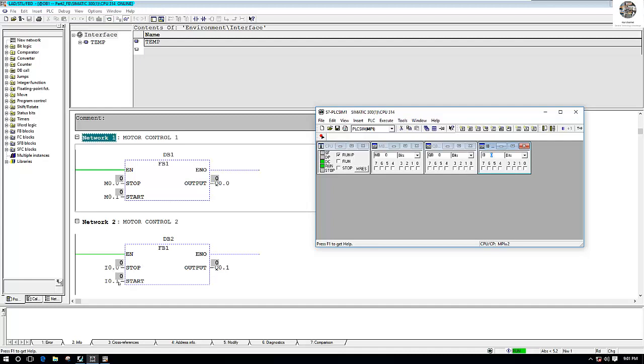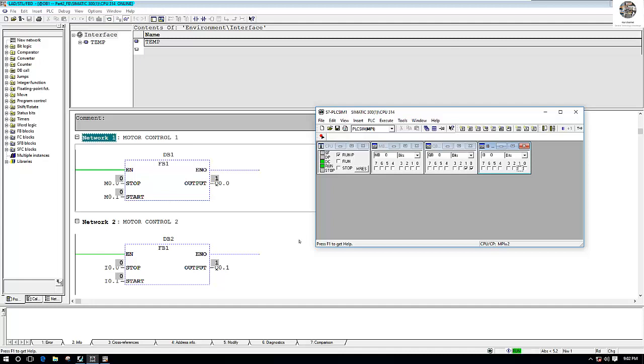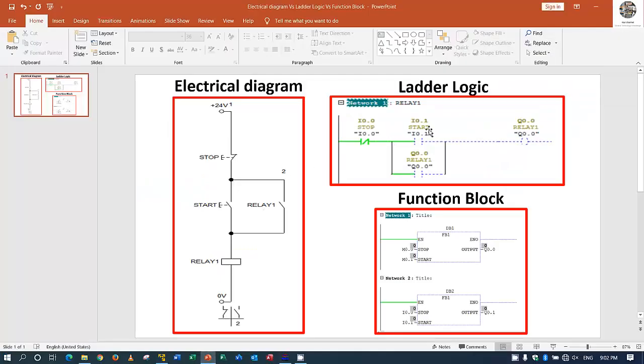It starts from I0.1 — so when I0.1 is ON, Q0.1 is ON. If we want to stop, we just turn ON the stop input and motor number two stops. So this is the concept: converting from electrical diagram to ladder diagram and then to function block diagram.